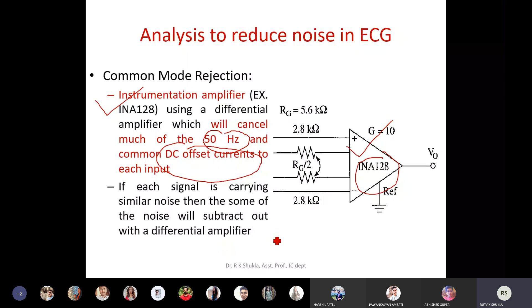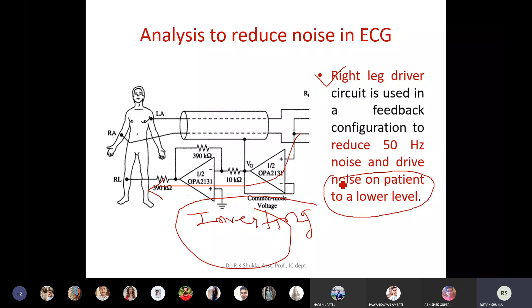The second line of defense is the right leg driver. The right leg driver circuit is used in a feedback configuration to reduce 50 Hertz noise and drive the noise on the patient to a lower level. We are sending part of the signal back to the patient by inverting its polarity. So ultimately what we are doing is reducing the noise on the patient.